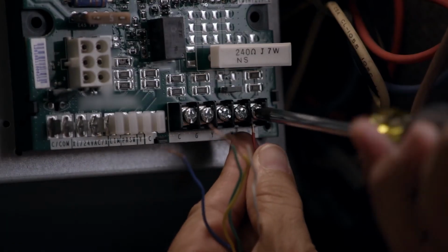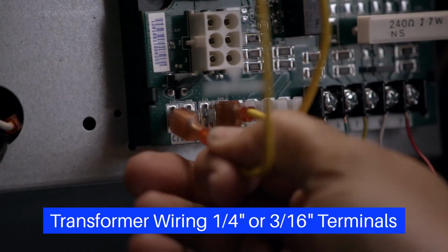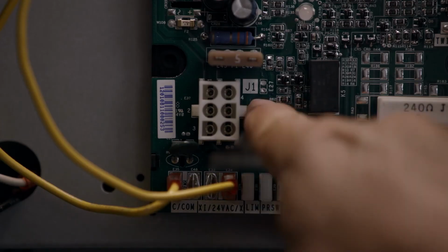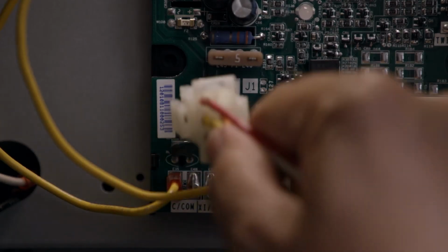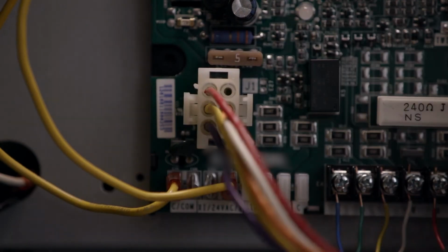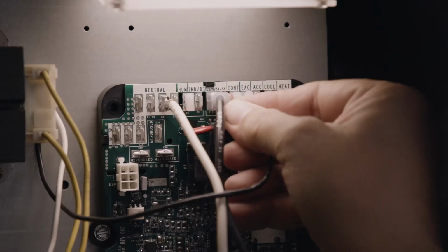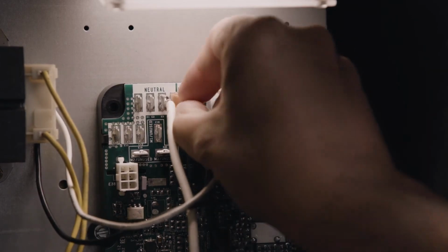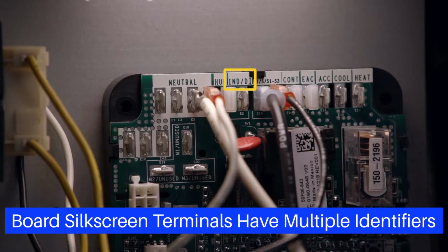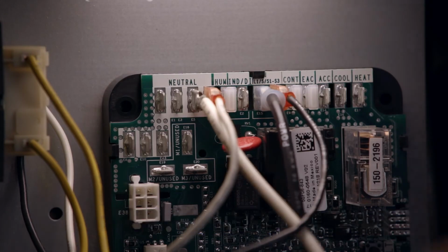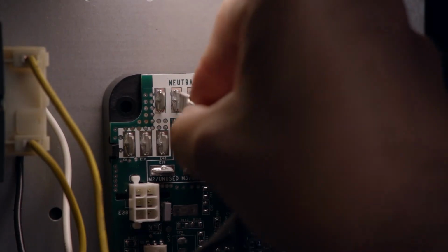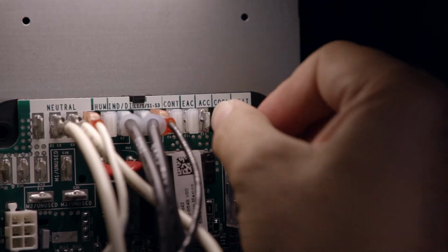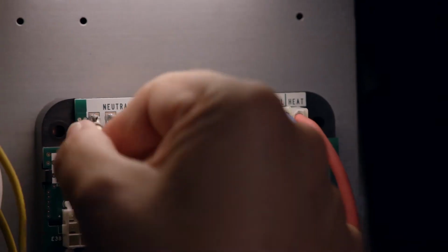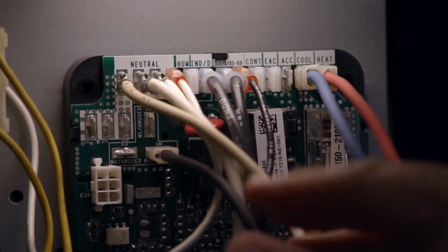Replace the thermostat wiring. Connect the transformer 24-volt power. Next, connect the 6-pin to J1. For this application, no harness is required. Reconnect the 115-volt power supply. Connect the transformer 115-volt supply. Connect the inducer power and neutral wires. Connect the blower motor heat, cool, neutral, and park wires.